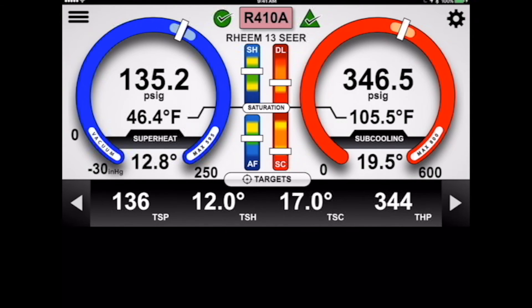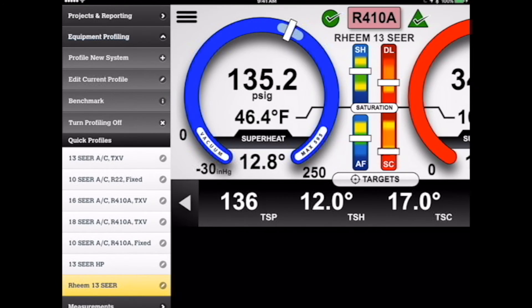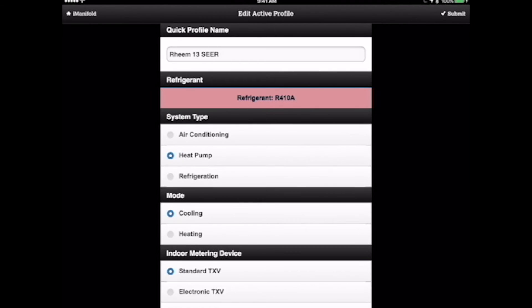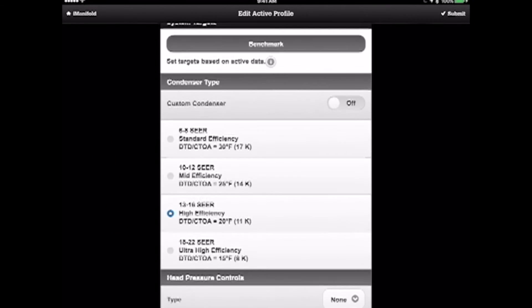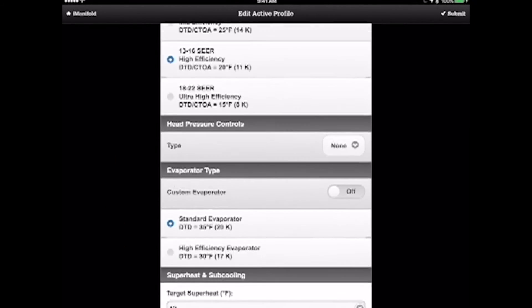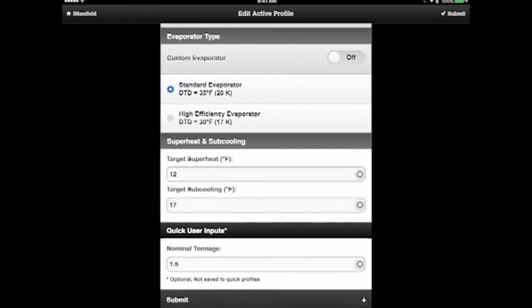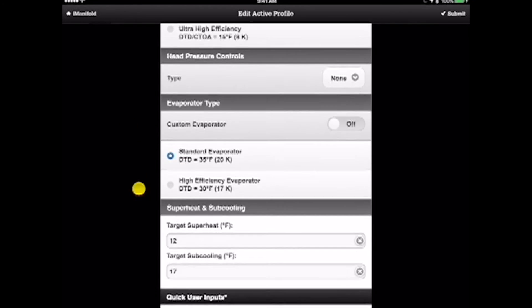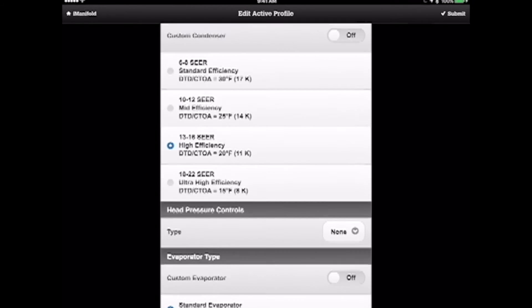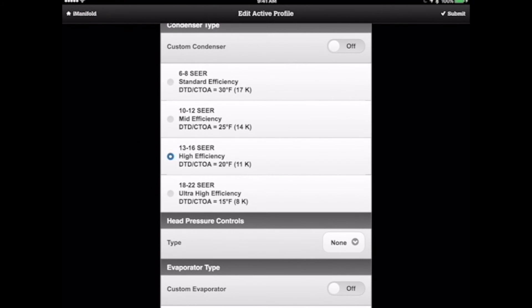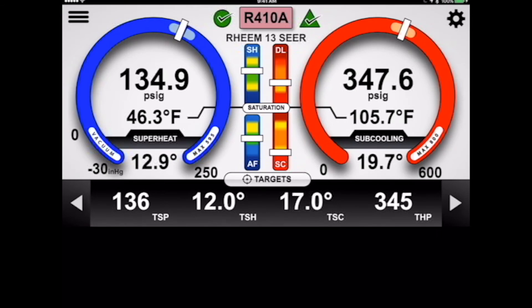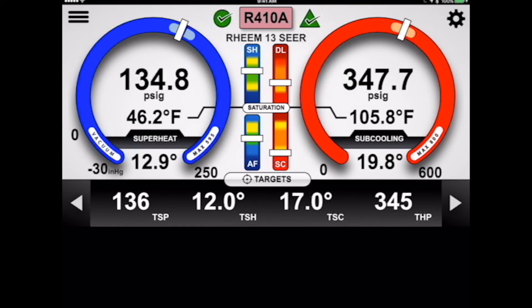Now, again, we haven't benchmarked the system yet. You can see how close that is if we edit that current profile. This is just a standard profile for a 13 SEER heat pump system, and those targets are pretty well nailed. It's looking pretty good just as it sits right now.